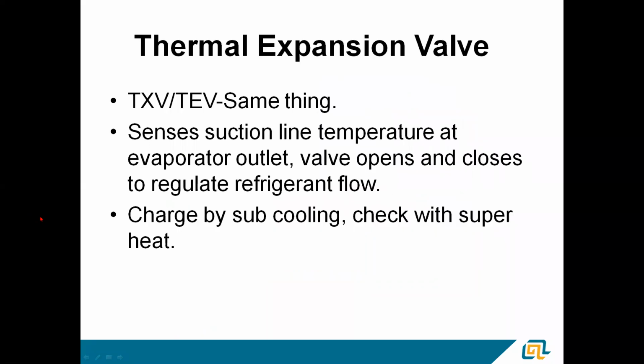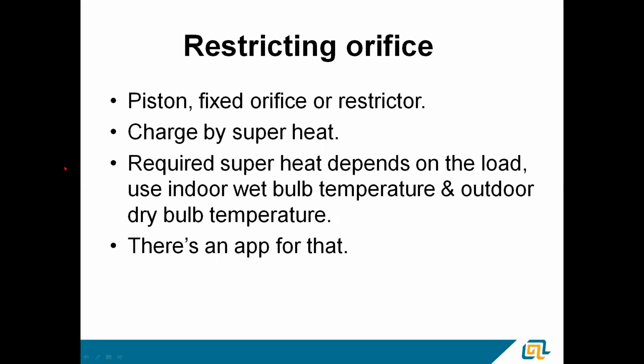Thermal expansion valves. You see them called either a TXV or a TEV. It's the same exact valve, just different connotations. They sense the suction line temperature at the evaporator outlet, and the valve will open and close to regulate the refrigerant flow to maintain superheat. Charged by subcooling, and you check with superheat. So you do have to check both readings.